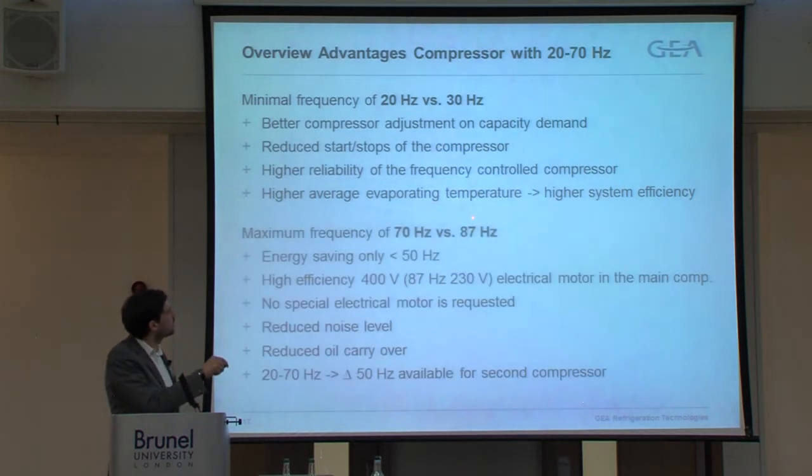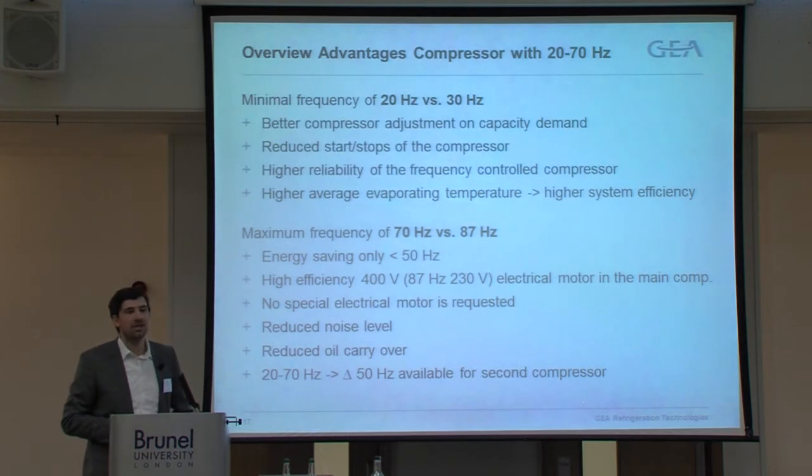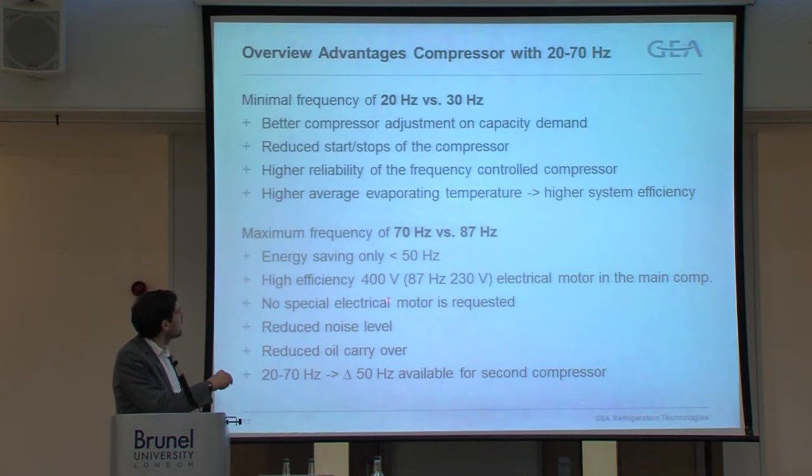On the other side, of course, there is an option to have 87 hertz, to have more capacity with the frequency-controlled compressor, but we recommend always to use 70 hertz combined with the 20 hertz. Then we still have a frequency range of 50 hertz for the second and the third compressor, because what we can see with the 87 hertz is that we can save energy only when we are running a compressor up to 50 hertz.